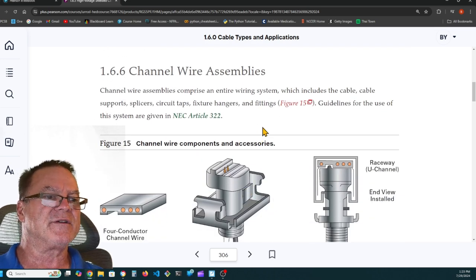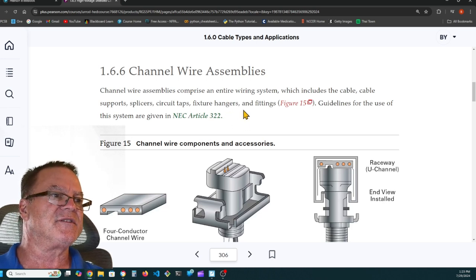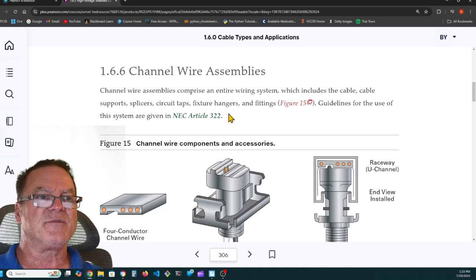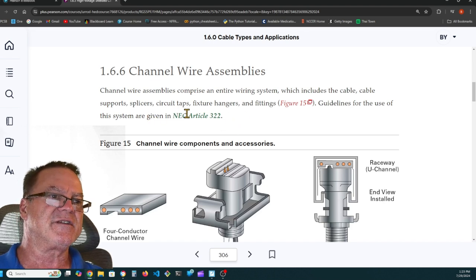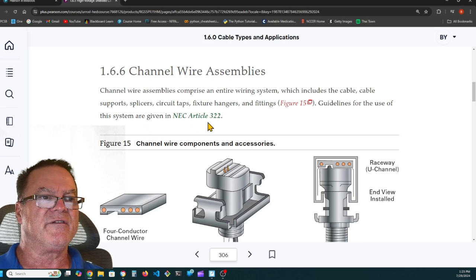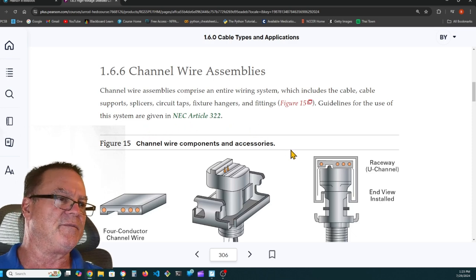1.6.6, channel wire assemblies. Channel wire assemblies comprise an entire wiring system which includes the cable supports, splicers, circuit taps, fixture hangers, and fittings. Figure 15. Guidelines for the use of the system are given in NEC Article 322.